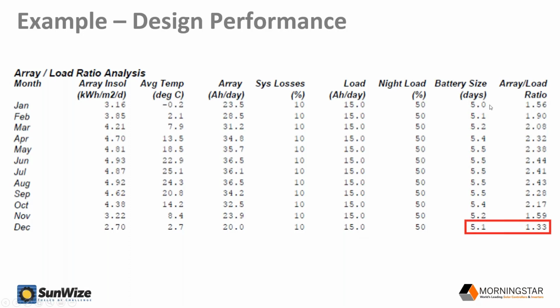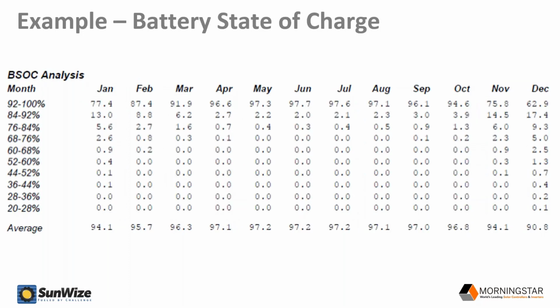And then in the last right 2 columns, you'll see our battery size that I alluded to. So in December, the worst case month, we've got at least 5.1 days of autonomy, and we've got an array to load ratio of 1.33. And again, we'll talk about this a little bit more in some of the next slides. The array to load ratio is essentially the ratio of energy produced by the solar array to the energy consumed by the load. It's essentially a safety factor or a design factor on the solar array side of things. We want that to be somewhere in the 1.2 to 1.4 range.